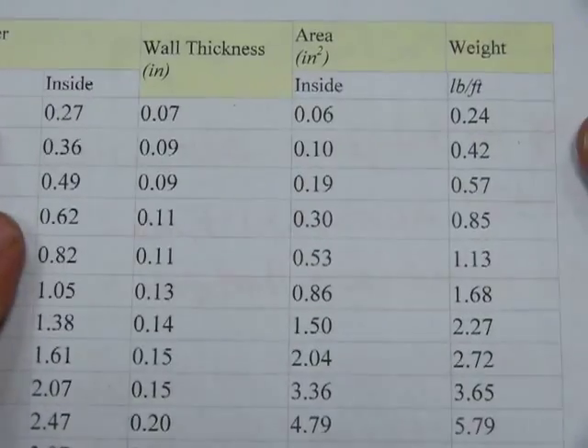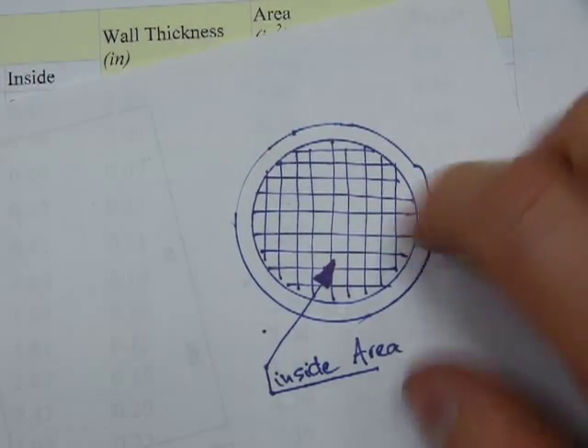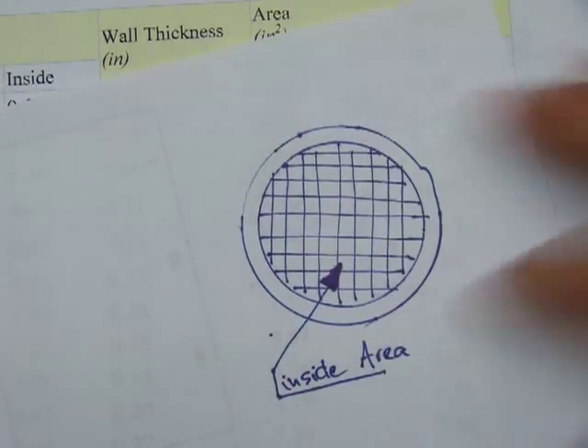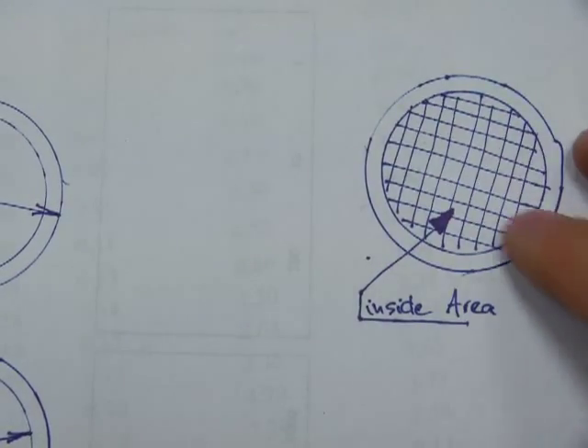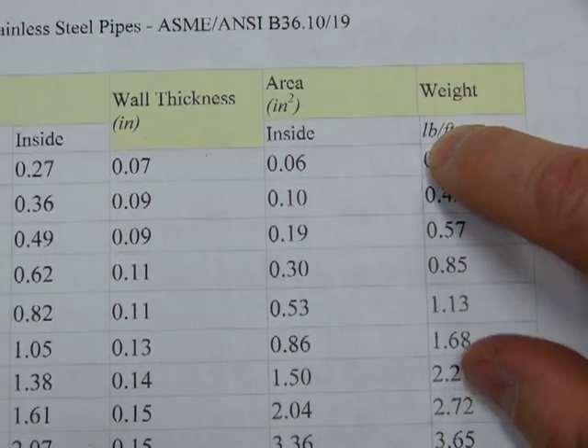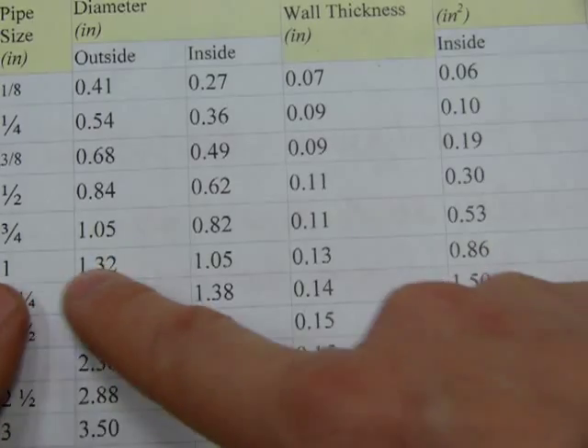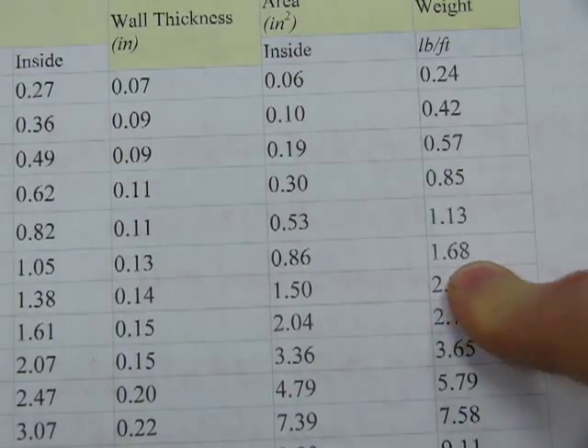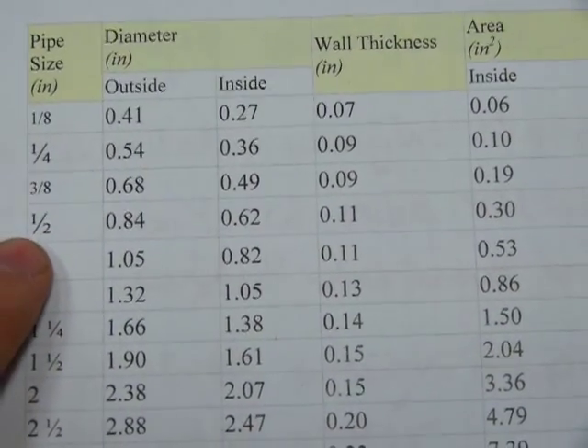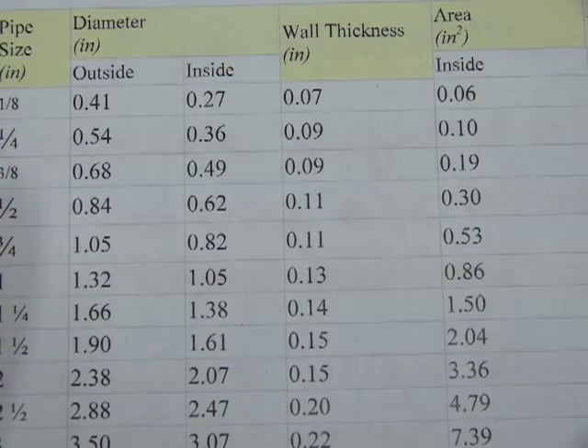Here is another table with wall thicknesses for standard pipe. It has a column of data for inside area — the cross-sectional hollow area inside the pipe, not the wall itself. Weight is again listed in pounds per foot of length. You can see that a one-inch Schedule 40 pipe has a weight of 1.68 pounds per foot, because this table works for Schedule 40 pipes only. So there are a couple of different formats and layouts for these tables. You will probably see a different one in your trades training manual, but that's the idea — what the information means in these pipe schedules.